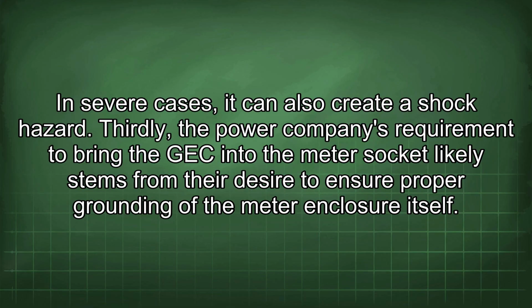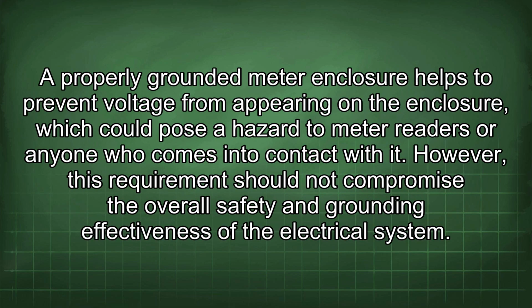Thirdly, the power company's requirement to bring the GEC into the meter socket likely stems from their desire to ensure proper grounding of the meter enclosure itself. A properly grounded meter enclosure helps to prevent voltage from appearing on the enclosure, which could pose a hazard to meter readers or anyone who comes into contact with it. However, this requirement should not compromise the overall safety and grounding effectiveness of the electrical system.